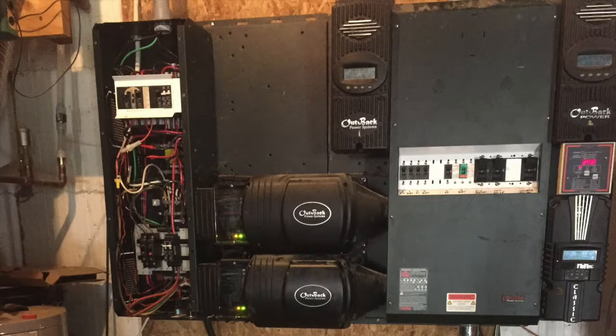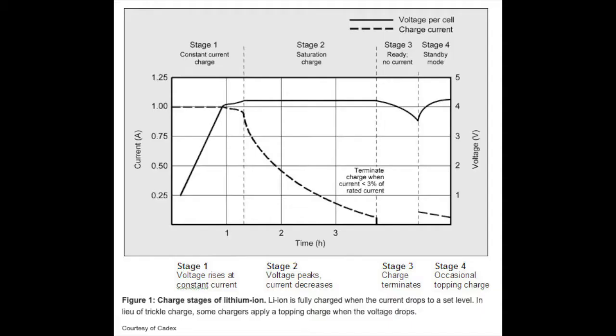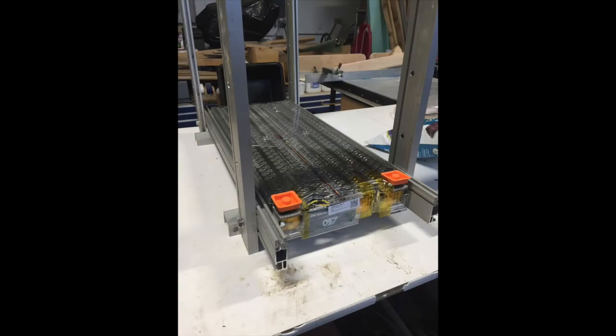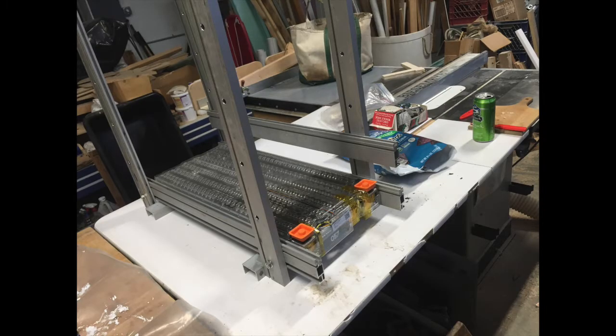These were retrofitted into a fairly conventional off-grid power system using Outback inverters and charge controllers. The lithium battery charge profile was pretty much at the outer limits of that equipment, but newer equipment is far more flexible. I built a rack for the batteries out of some salvaged aluminum PV rail. The tabs on the batteries fit nicely into the slots on the rail, making for a pretty nice slide-in, slide-out scenario.